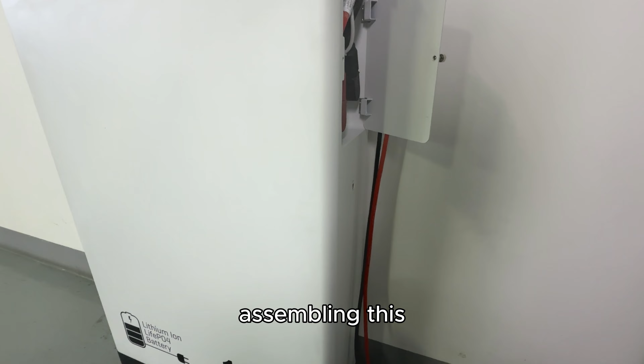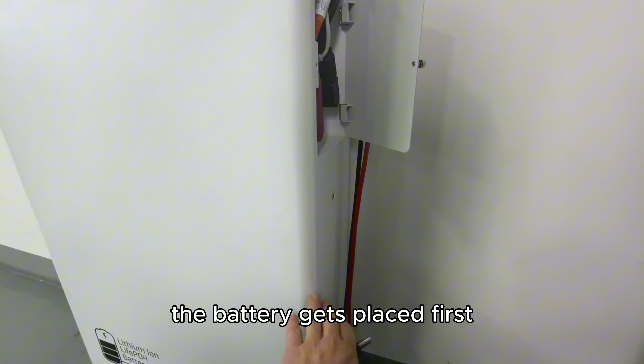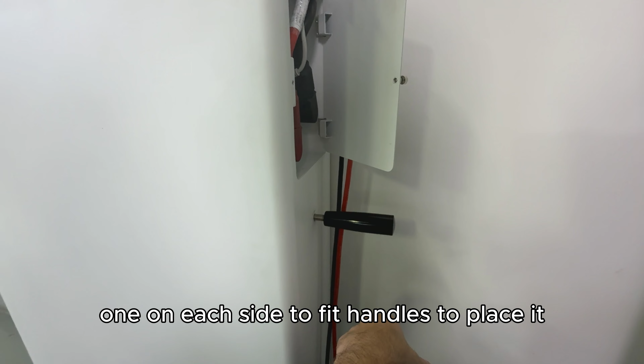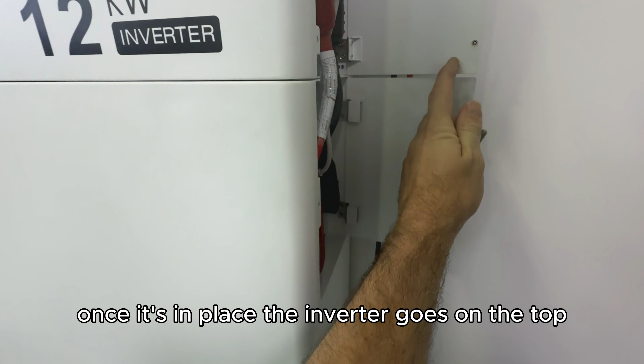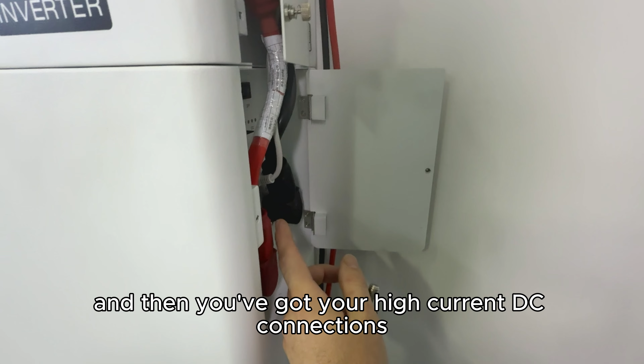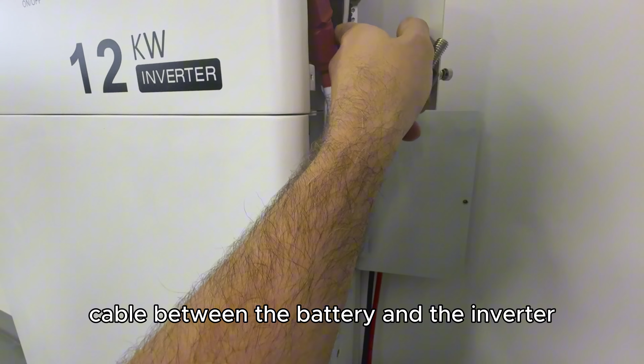Assembling this HESS or BESS battery energy storage system, the battery gets placed first. There's two M10 threads, one on each side to fit handles to place it. Once it's in place, the inverter goes on the top, and there's an M8 fastening front and back on both sides. And then you've got your high current DC connections and your communications cable between the battery and the inverter. And that's all you need to get it going.